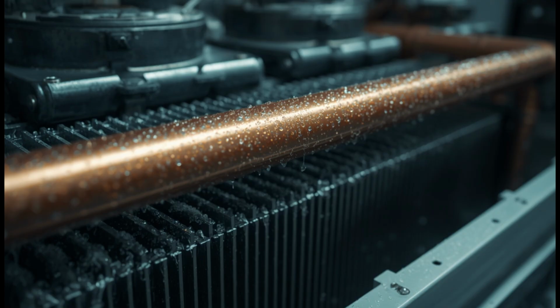Here, rather than hot water from a boiler, chilled water arrives instead, sent from the chiller plant elsewhere in the building, water cooled through its own separate, elaborate process, arriving at the coil already carrying a temperature far below that of the air about to pass across it. In other buildings, rather than chilled water, the coolant coil might instead hold refrigerant directly, a system engineers refer to as a direct expansion coil, in which the refrigerant itself expands and cools within the copper tubing, absorbing heat directly from the passing air without any water serving as an intermediary. Both approaches accomplish the same essential task, differing mainly in the equipment required to prepare the fluid that ultimately does the cooling.